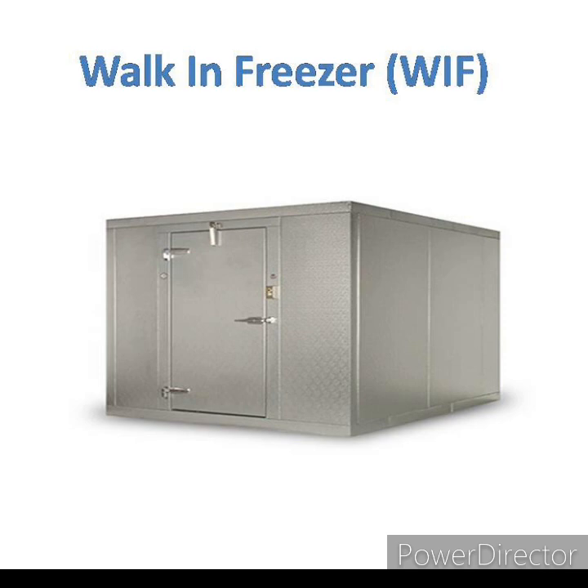Taking cold chain equipment one by one — first, the walk-in freezer or WIF. These are pre-fabricated modular polyurethane insulated panel rooms where temperature is maintained from 0 degree to minus 20 degree centigrade. They are called WIF because you can walk inside the room which maintains freezing temperatures. These rooms are installed with refrigeration units, a temperature meter, and an alarm system. They are used for storing OPV and frozen ice packs at state or regional level, with a usual storage capacity of 15 to 20 lakh doses or more.